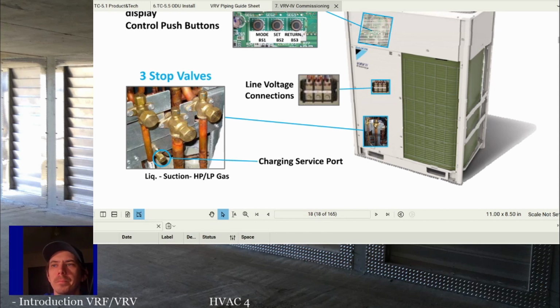So on older systems, what they would do is they would have a tube that connected from each outdoor unit, and that would equalize the oil level between the multiple compressors. So if you had a 3 outdoor unit system all interconnected with 6 compressors, you need to make sure you have the right amount of oil in all 6 compressors. And you add a lot of refrigerant to these systems when you install them. You don't add any oil.